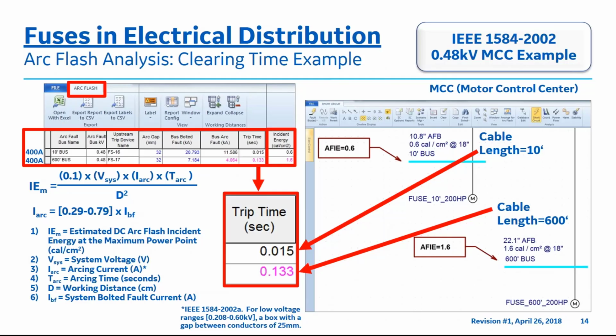In this clearing time example for fuses, the 10-foot cable with the arcing current trip time, noted as the arcing time, or T-arc, has the influence on the arc flash incident energy label from the arc flash analysis report, with a corresponding clearing time of 0.015 seconds, which reflects the lower arc flash label of 0.6 calories per centimeter squared, shown on the right.